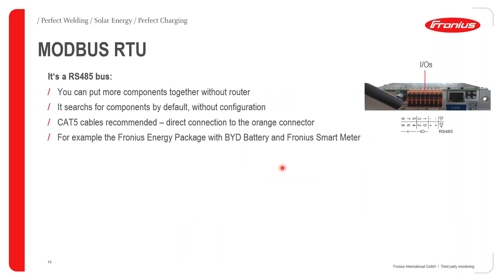Looking at the features of our Modbus RTU: it communicates via the RS-485 communication bus. You can put multiple components together without necessarily using a router, and it searches for connected components by default without any necessary configuration. We recommend CAT5 and above cables and twisted pair wiring.